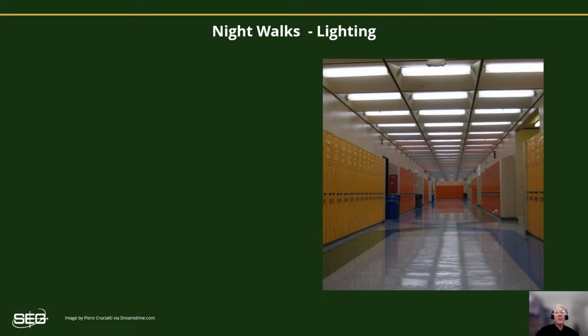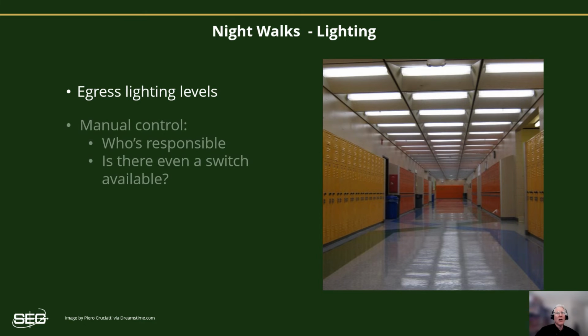Lighting may be the most obvious opportunity you'll encounter during a night walk. You'll likely notice that most buildings will have some emergency or egress lighting running all night, but it should be minimal, just enough to allow safe egress from the building when it's dark. Make a note to investigate it if it seems excessive. Also note any rooms, hallways, or section of the building with many lights still left on. The hallway in this picture is a real example from a high school at night. In this case, there were no accessible switches for the custodial crew to use to shut the hallway lights off, so they were just left on, always.